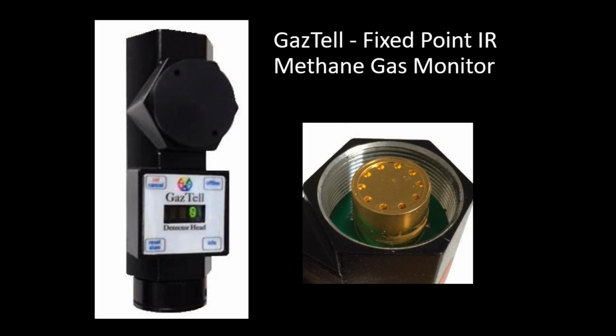As you can see by the picture, by the way, the optical chamber is very, very small. And the amplification of signal, if you could imagine how much a photon of light can absorb one molecule of gas, you can see that the amplification of the signal is critical in giving you good gas detection. And that's where success or failure is when you design a gas detector, that you have to make sure that everything works together as a team.